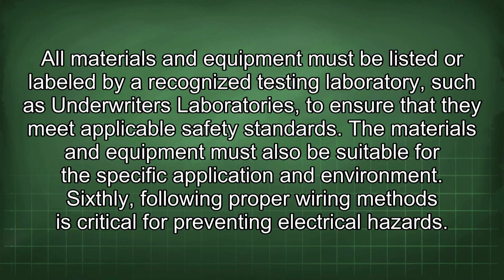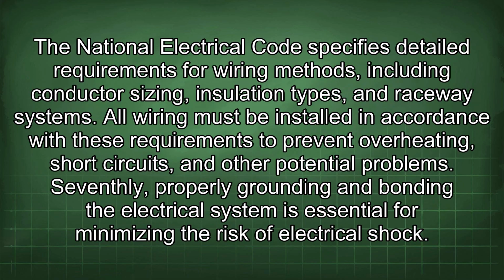Sixthly, following proper wiring methods is critical for preventing electrical hazards. The National Electrical Code specifies detailed requirements for wiring methods, including conductor sizing, insulation types, and raceway systems. All wiring must be installed in accordance with these requirements to prevent overheating, short circuits, and other potential problems.